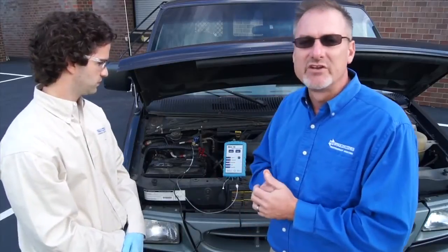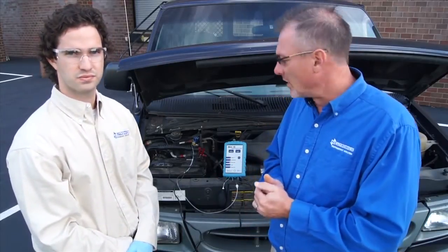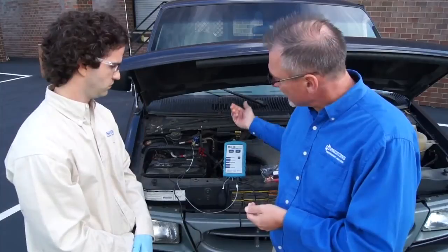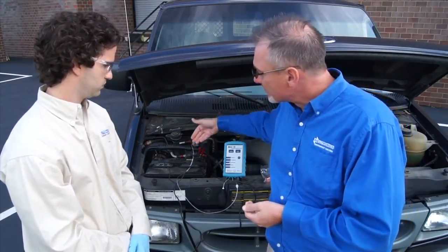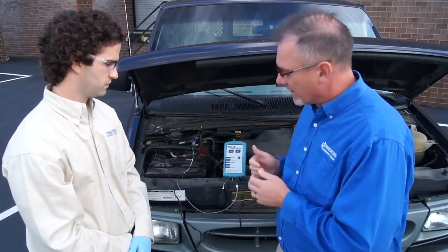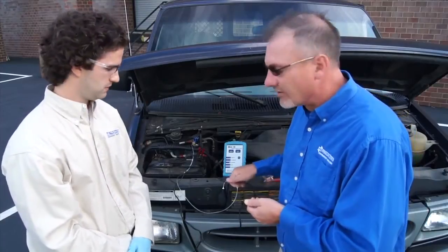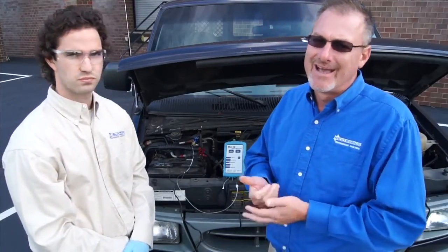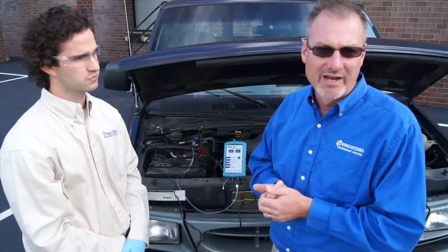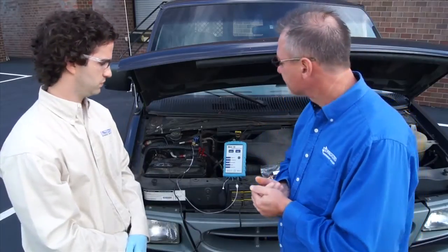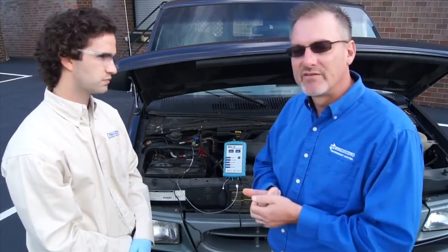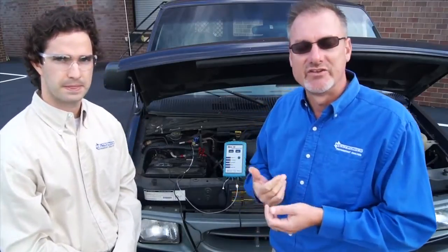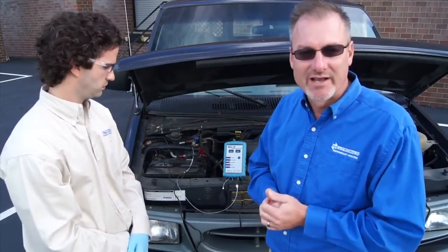A very small amount of vapor refrigerant is flowing out of the service port into the flow restrictor, through the hose, and into the analyzer, and it exhausts down here out of an exhaust of the analyzer. And we're only using just a couple of grams of refrigerant here. If you were to get a fault light, that means there's an error and you've got to call us. It's in the operating manual how to reach us.